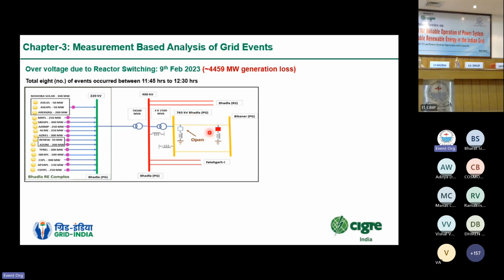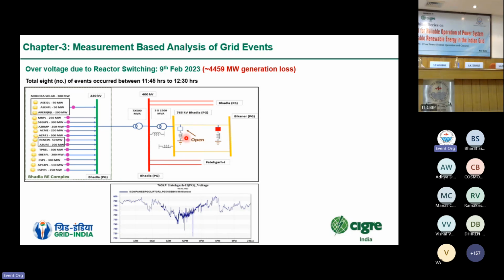So the first question that comes to mind is why the requirement of opening this line reactor arose at that point. Because of the lack of reactive power support from some of the plants, we witnessed low voltages during high solar hours. Because of this, we had to open even the switchable line reactors along with all the bus reactors, so all the measures that we could take to maintain the voltage near the nominal value were taken. During one such operation, we witnessed this generation loss of around 4,500 megawatts.